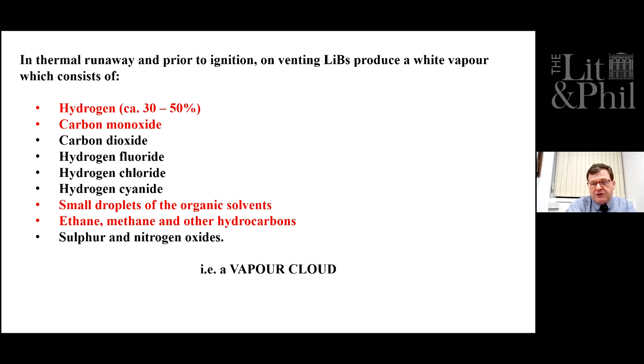What's emitted is hydrogen, up to 50%, carbon monoxide, carbon dioxide, and a series of very toxic gases: hydrogen fluoride, hydrogen chloride, and hydrogen cyanide. Also gases such as ethane, methane, and other hydrocarbons, plus small droplets of organic solvent. This gives a thick white appearance, which has been mistaken for smoke or steam, but it is in fact a vapor cloud.